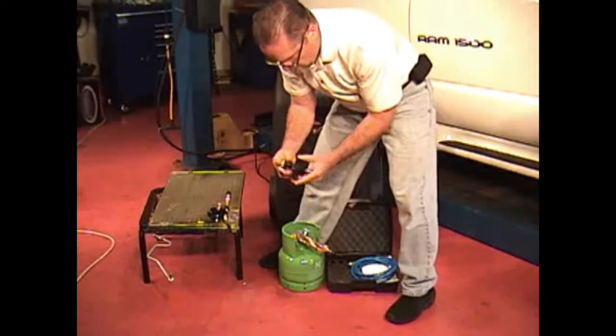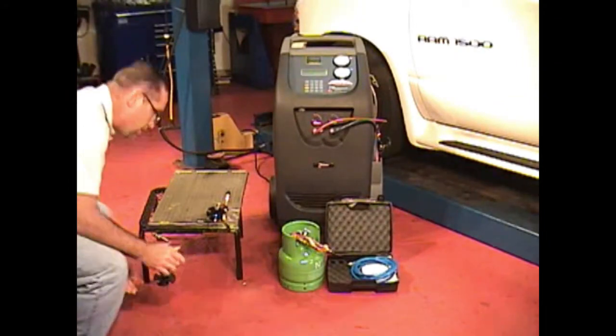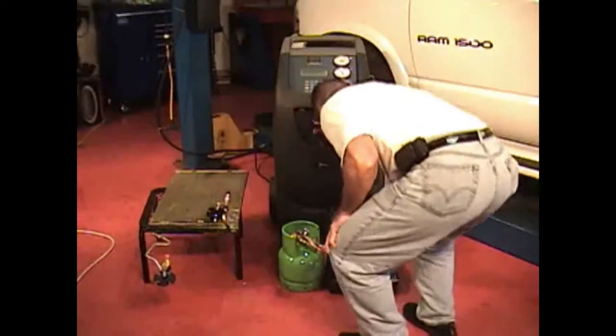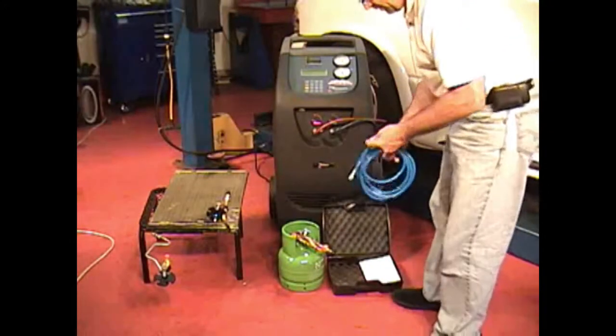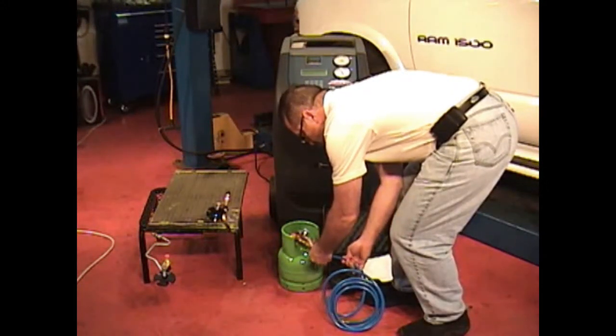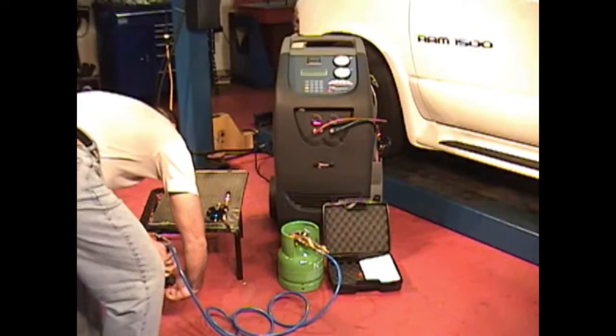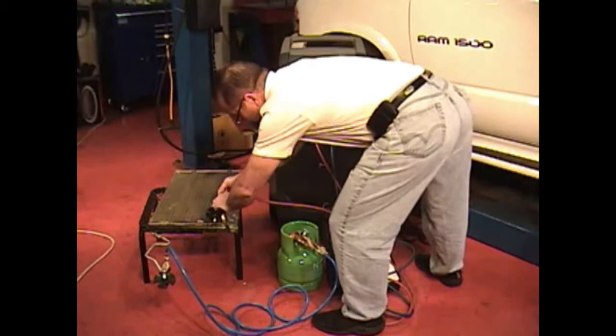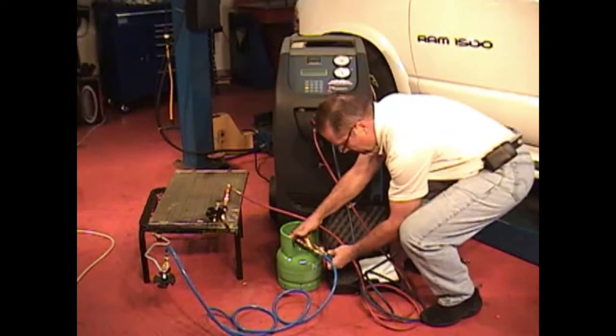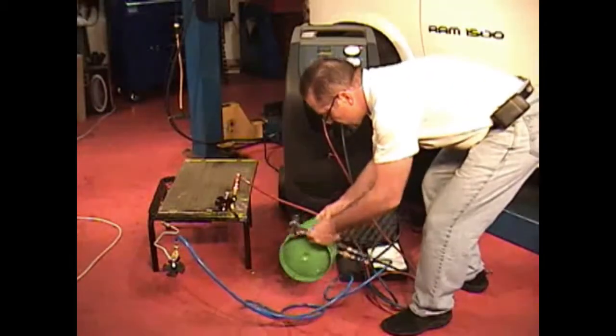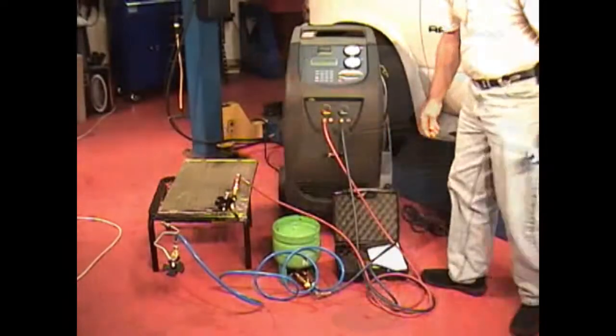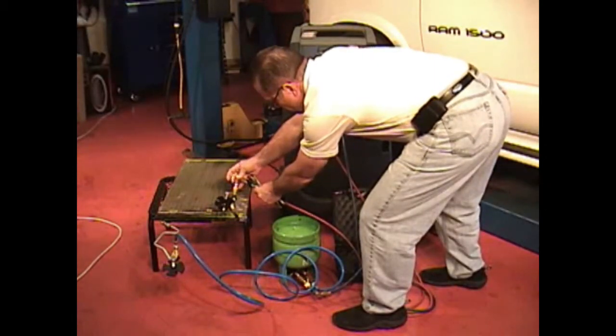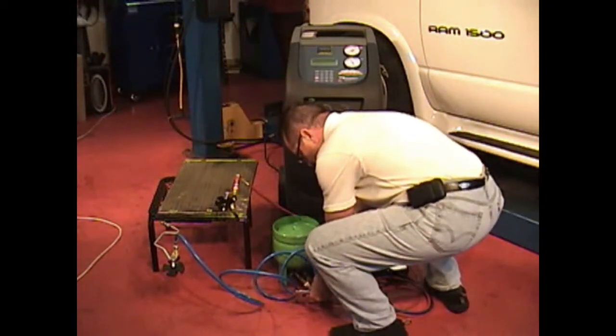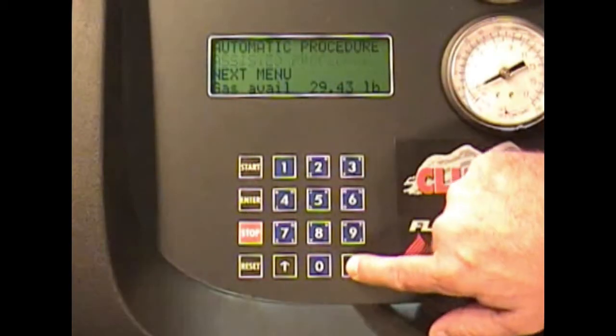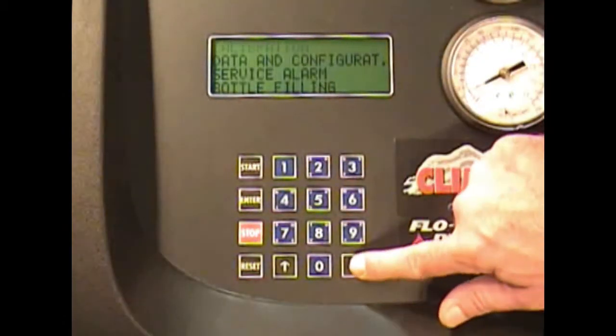Now connect the outlet universal adapter to the other component port. Connect the blue hose between the outlet universal adapter and the filter fitting. And connect the high side coupling to the inlet adapter and the low side coupler to the sight glass fitting. Open the valves on the surge tank and turn it upside down. Open both service couplings. Once connected, go to the next menu, then AC System Flushing.